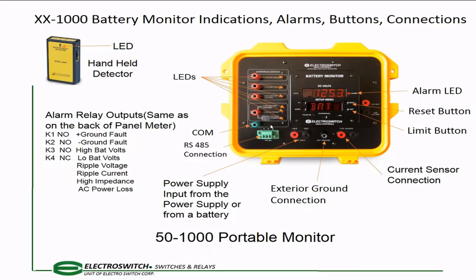This is the portable unit showing, once again, the LEDs for all the various alarms. You have the RS-485 connection. This is a common when you're hooking up external connections for the LEDs. And exterior ground, this is the current sensor, limit, reset, and alarm buttons. Alarm LED, this is the LED for the alarm. It would come on here, and then it'll come on your LED showing you which alarm is actually operating. The reset button is for when you have an alarm that's latched in, and that's one of the features. You can latch them in or not latch them in. And this limit button is designed to allow you, from the front of the panel, to set your battery voltage, all your alarm features and all your system features that you're going to use.